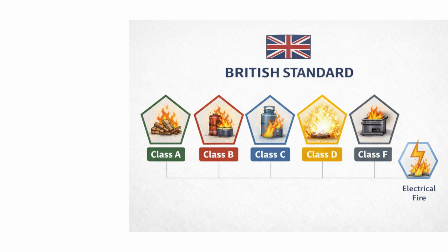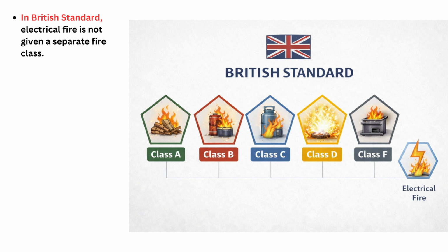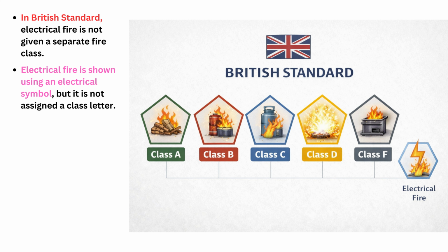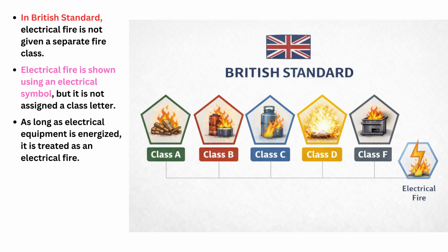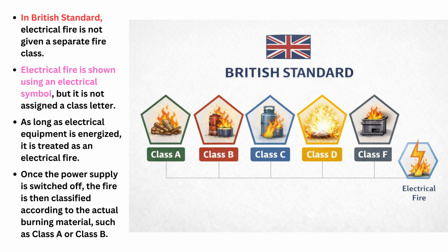When we talk about the British standard, electrical fire is not given a separate fire class. Electrical fire is shown using an electrical symbol, but it is not assigned a class letter. As long as electrical equipment is energized, it is treated as an electrical fire. Once the power supply is switched off, the fire is then classified according to the actual burning material, such as Class A or Class B. This point is extremely important for interviews.